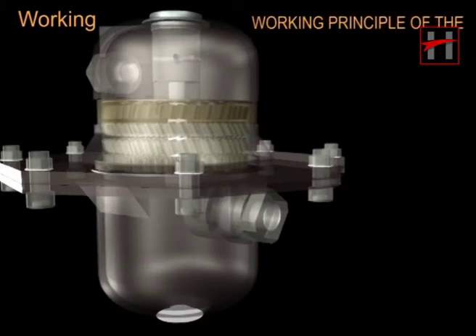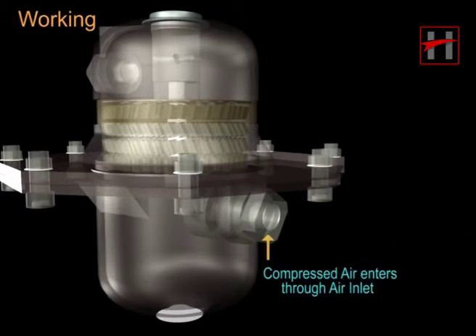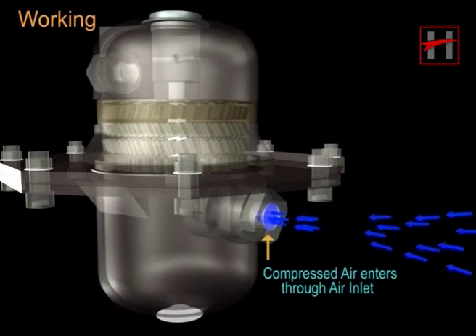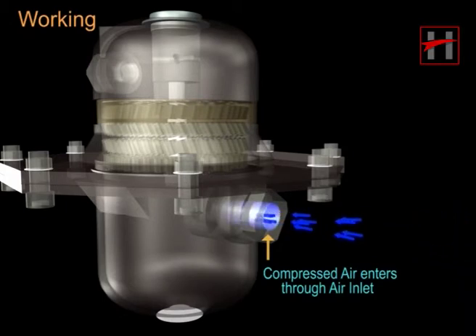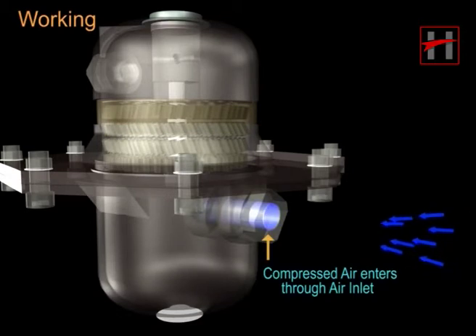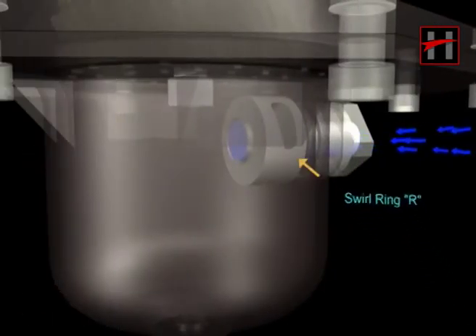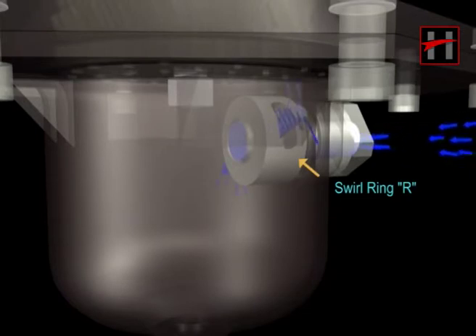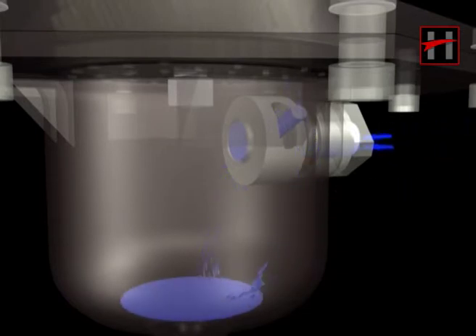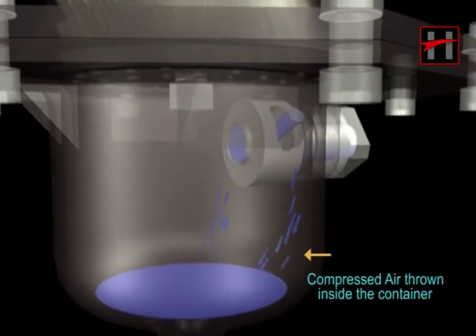The working principle of the oil separator is as follows. The compressed air enters the bottom part of the oil separator through the air inlet. The swirl ring at the inlet union redirects the compressed air and throws it against the inside of the container.